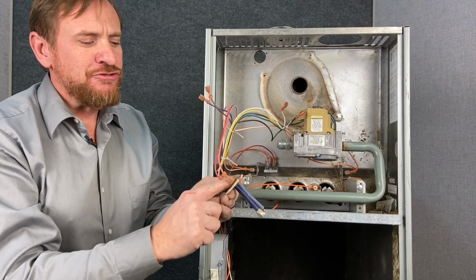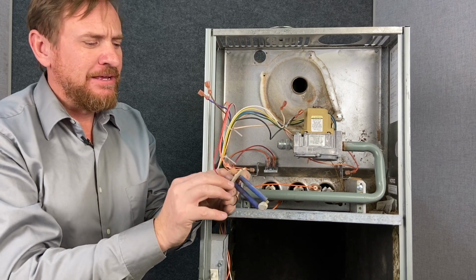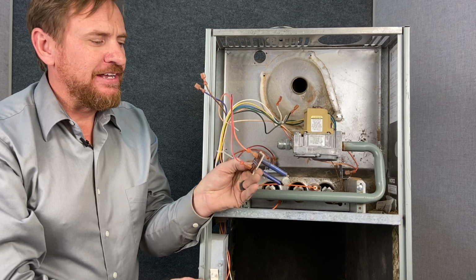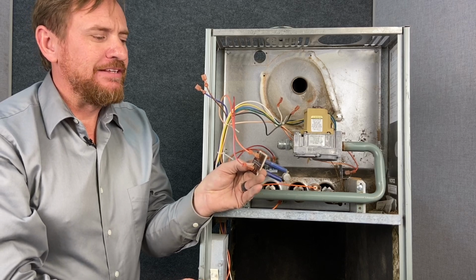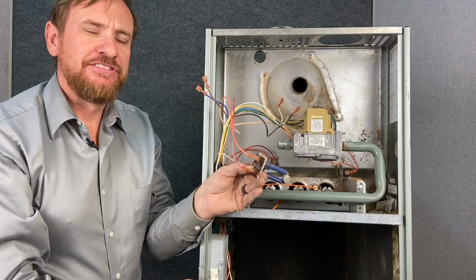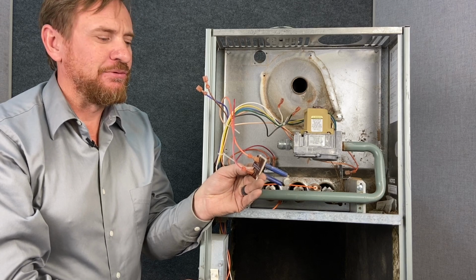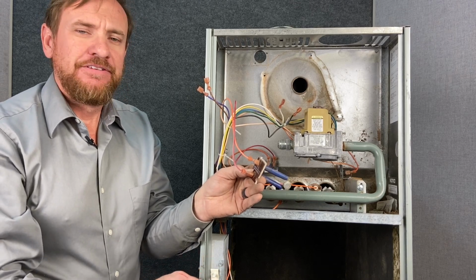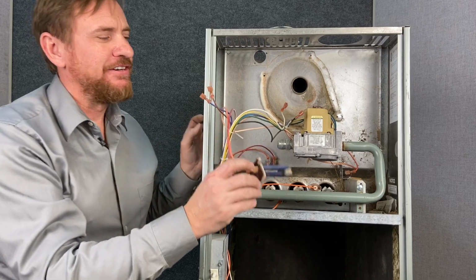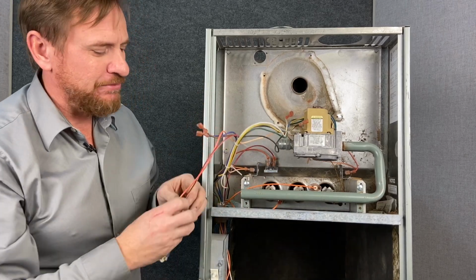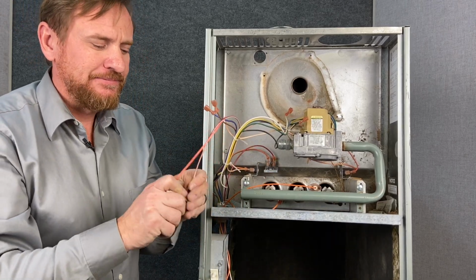And it has all these numbers rating on here. This one limits at 170 degrees Fahrenheit minus 20. That means it will reset 20 degrees less. So 170 minus 20, so we're looking at 150. So it resets at 150. That's our primary limit. So we're going to unplug it, and we'll take it out of the way.